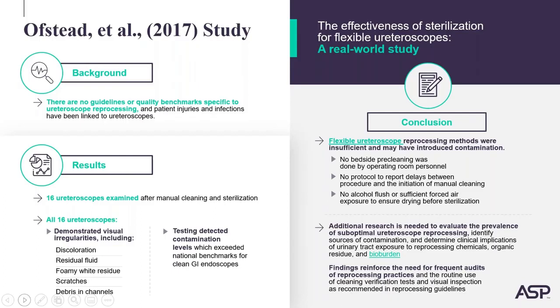They noted that no bedside point-of-use pre-cleaning was performed by OR personnel. No protocol was in place to report delays between procedure and the initiation of manual cleaning. And no alcohol flush or sufficient forced air exposure was performed to ensure drying before sterilization. Now, the OR managers stated these steps were performed by OR staff, but the observers did not see them in action, and OR staff acknowledged they did not routinely practice these. Findings of this study reinforce the need for frequent audits of reprocessing practices and the use of cleaning verification tests and visual inspection as recommended in reprocessing guidelines.